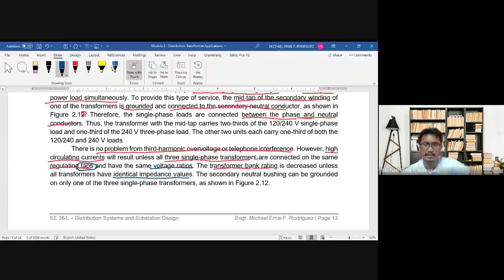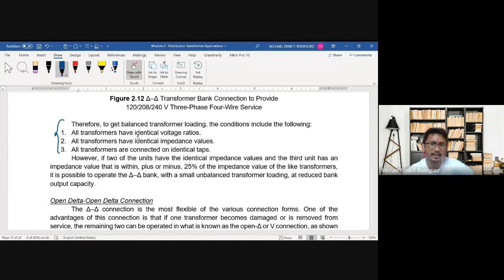So for a balanced transformer loading, we need these three: identical voltage ratio, identical impedance values, and connected on identical taps, so that the transformer loading is balanced.